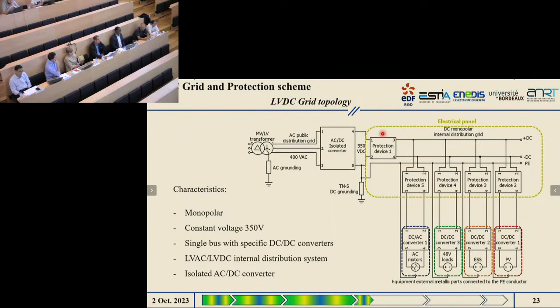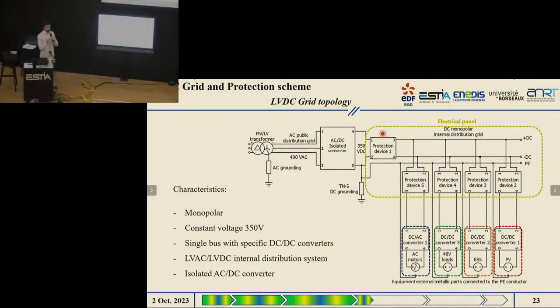I think what we tried to do was guarantee a certain safety from the point of view of the converter. So if we have a short circuit larger than 60 amps, meaning the converter is not able to saturate the current, and we can reach 70 or even 100, the proposition was to have a faster protection device in order to stop the short circuit, avoiding damage to the AC to DC converter.